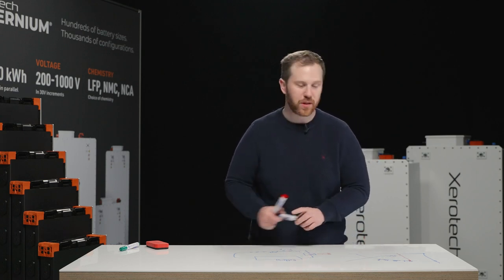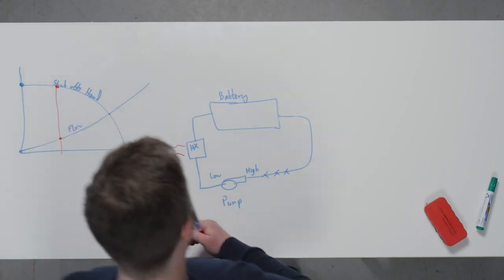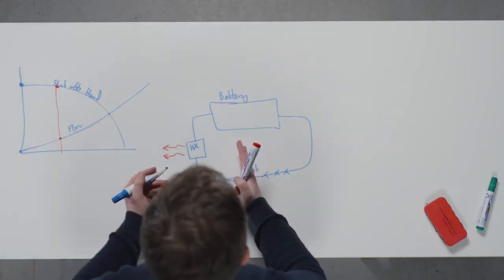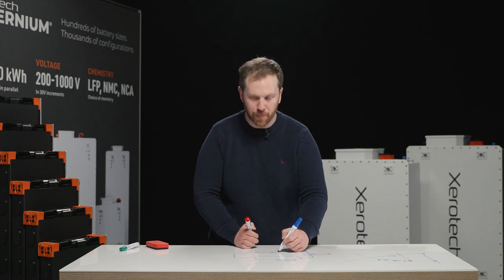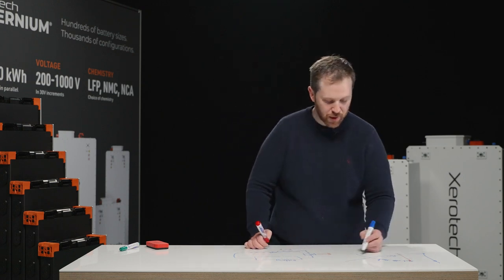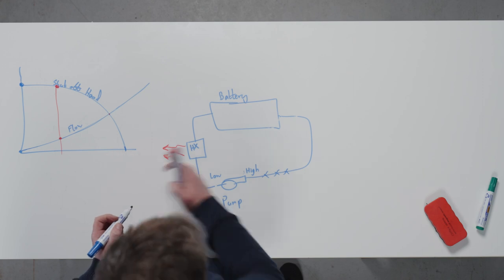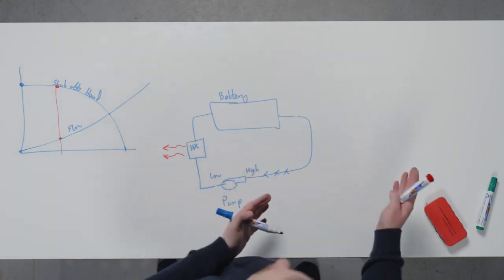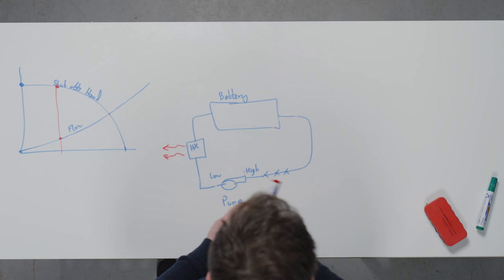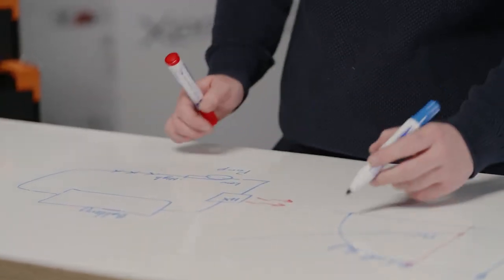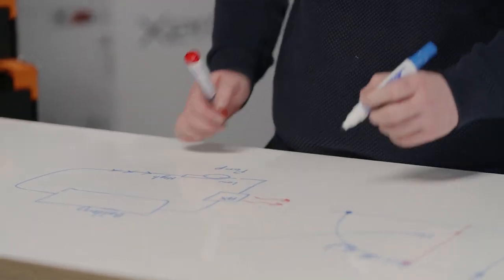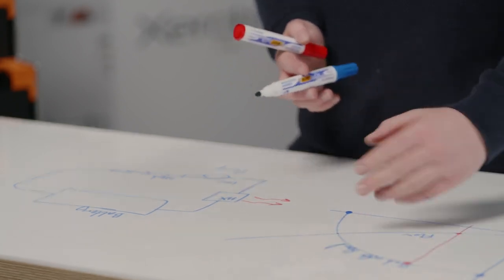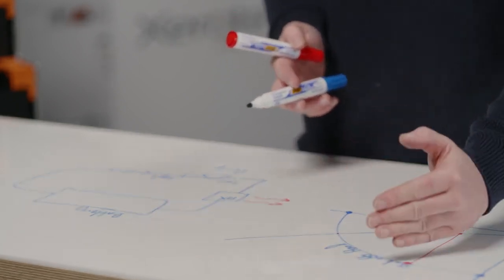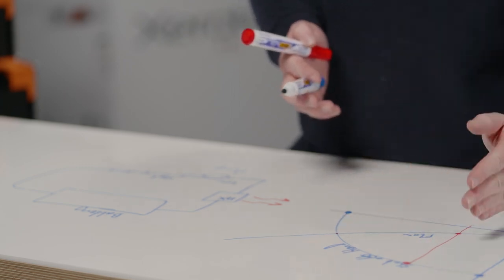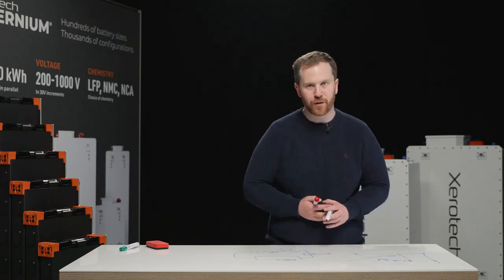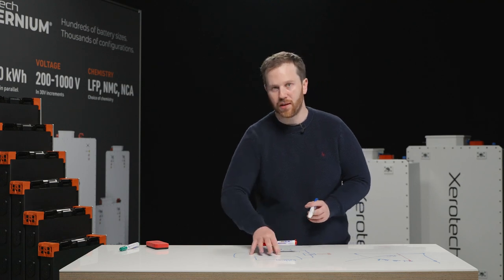So this graph has two extremes. The shut-off head, where if you completely block off the pump, you'll have zero flow and you'll have a maximum pressure on the pump. Or the other extreme case is where you've got zero back pressure here. Effectively, you're pumping into a vacuum, an ideal closed loop where the pump is just going around on itself. You develop the maximum flow in that scenario. In a real system, it's going to be somewhere between the two, probably closer to the top there. So you'll have some restriction on the flow rate. That's the first fundamental rule of pumps and how you lay out and design your system.